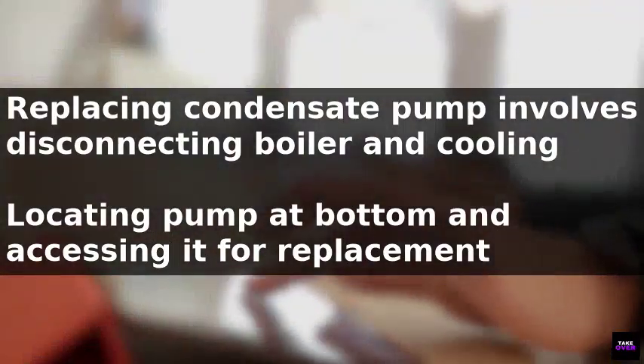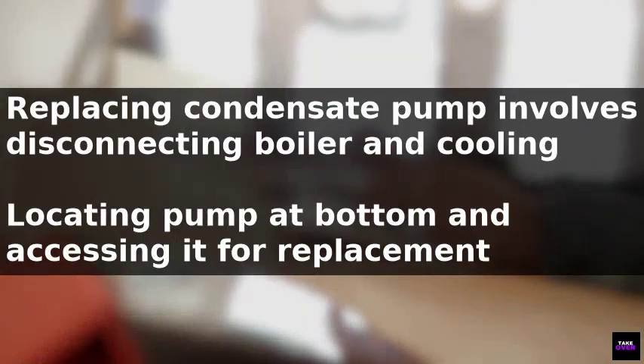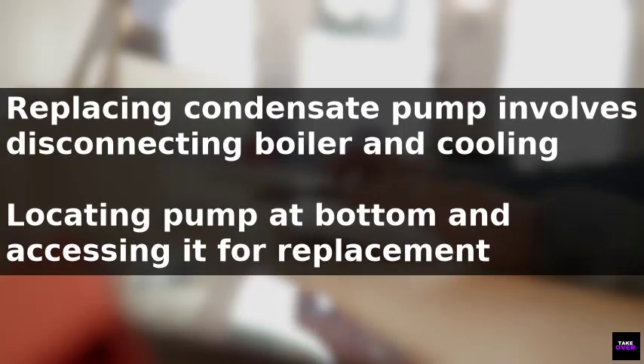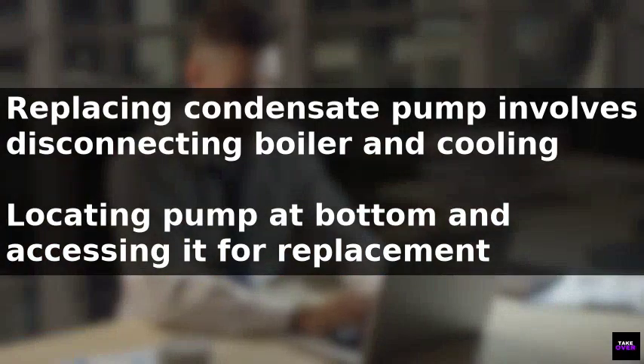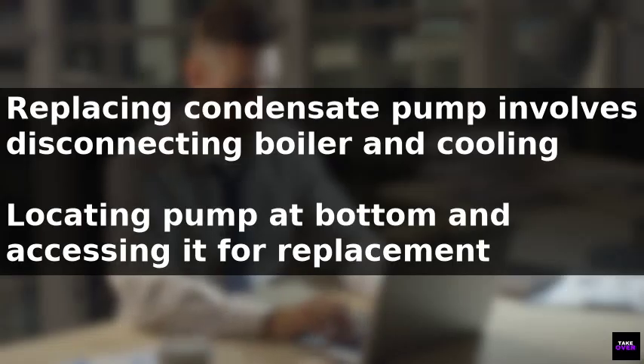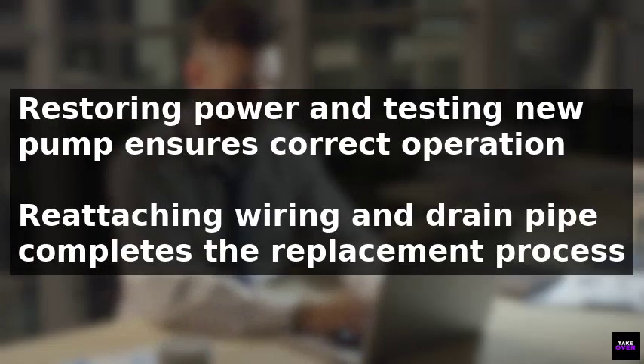To do this, the boiler should be disconnected and allowed to cool. Then the condensate pump, usually located at the bottom, should be accessed. The drain pipe should be disconnected, and any residual water emptied into a bucket. The wiring and check valve should then be disconnected and set aside.